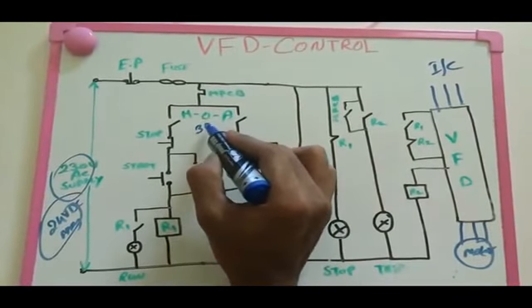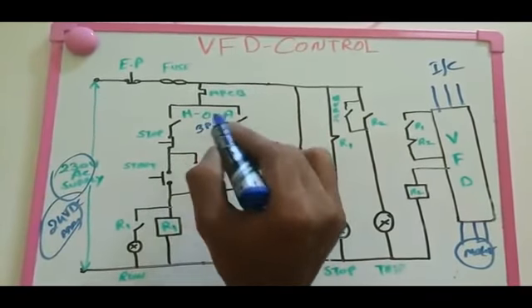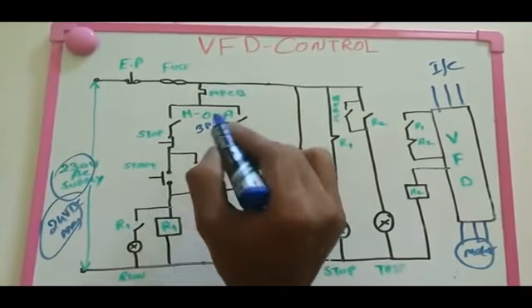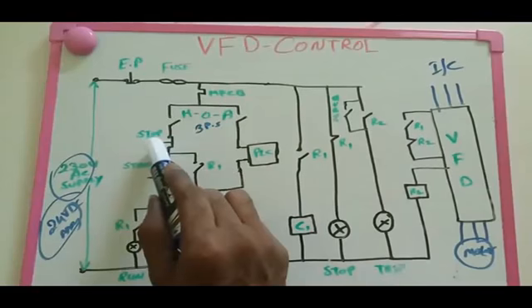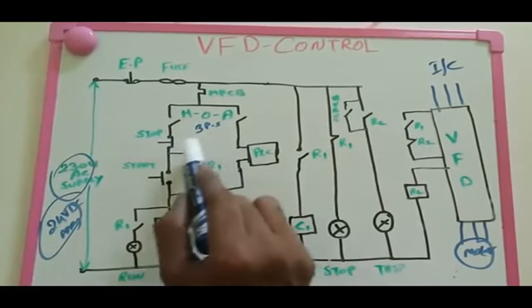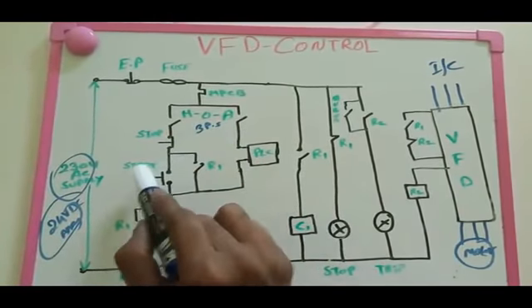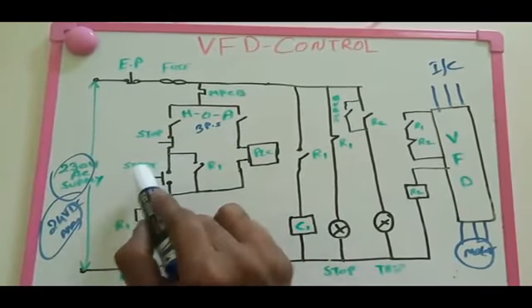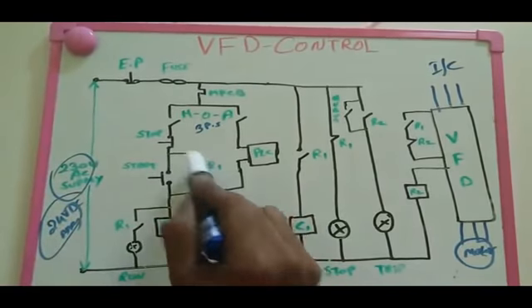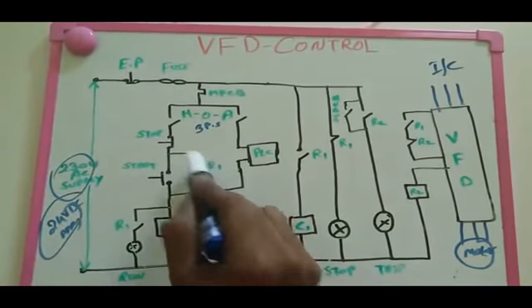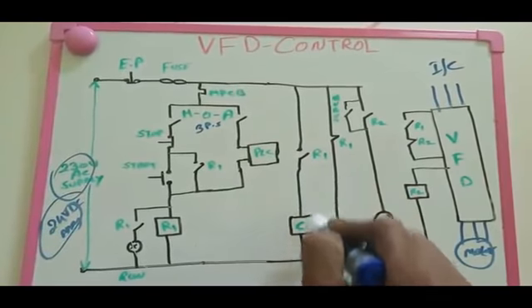Here is the three-position switch - that means hand, off, and auto. You can select three modes: hand operation, off, or auto operation. Here we select hand. This is the stop push button. This part is called hand operation. When you press start, the R1 coil is energized. When you release the start push button it goes back, so that's why we put the R1 NO contact here so the circuit remains continuously switched on.